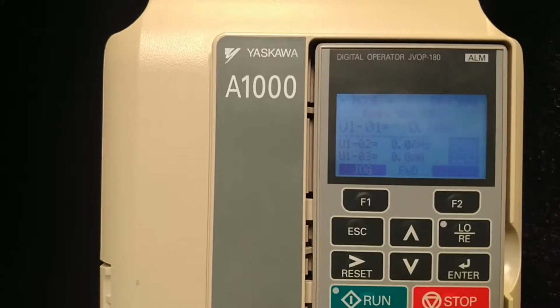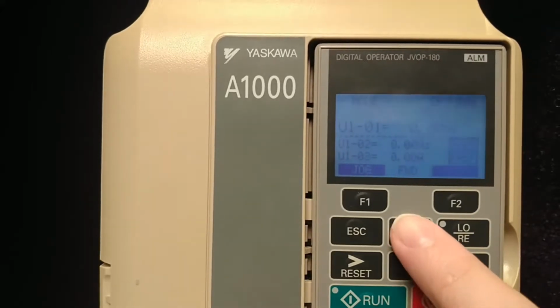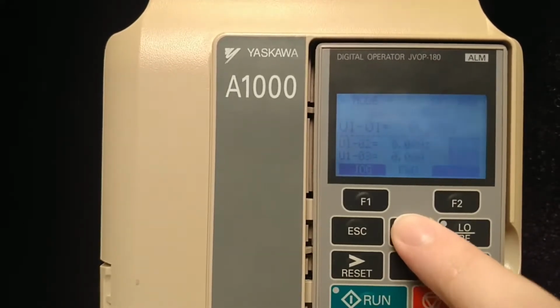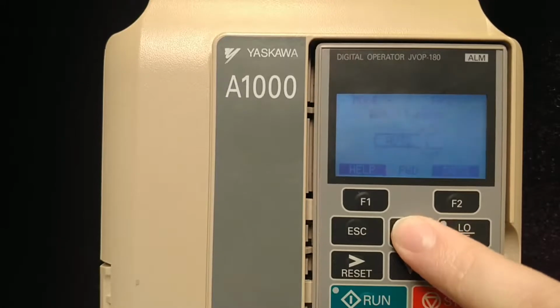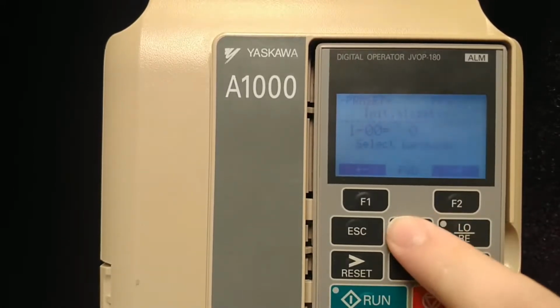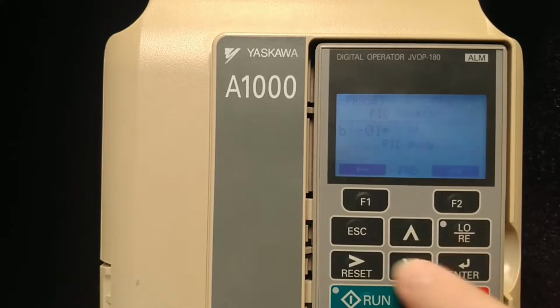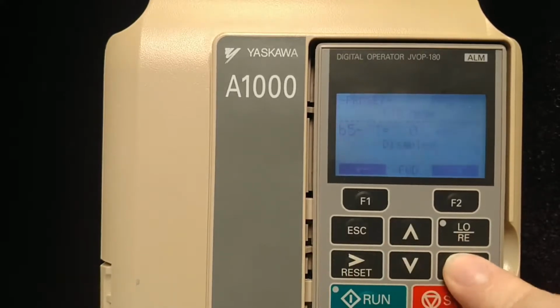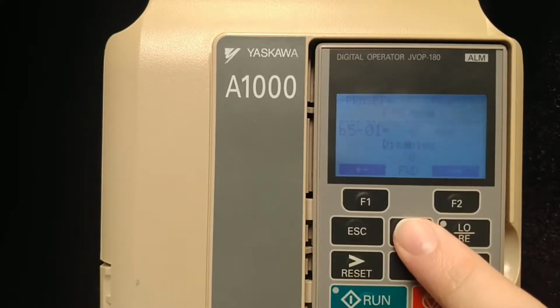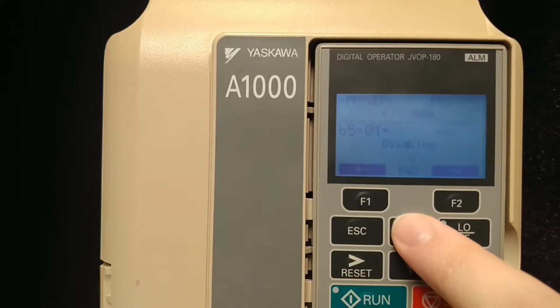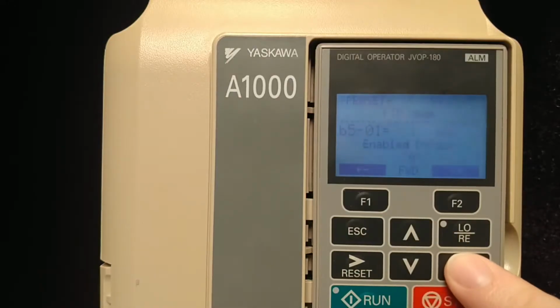Today I'll be going over setting up PID, PID scaling, and a set point for 1000 series drives excluding the IQ pump. The first parameter that you need to set to use PID is B501. B501 enables or disables PID mode on the drive. To enable PID mode, B501 needs to be set to a 1.